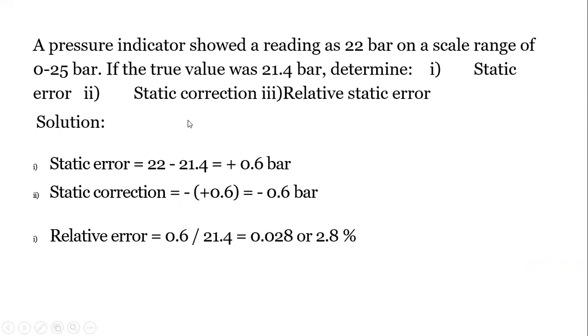A pressure indicator shows a reading of 22 bar on a scale range of 0–25 bar, with a true value of 21.4 bar. The static error is 22 − 21.4 = +0.6 bar. The static correction is −0.6 bar. The relative error with respect to true value is 0.6 / 21.4 = 2.8% of true value. It can also be expressed as 0.6 / 25 as a percentage of full scale deflection.